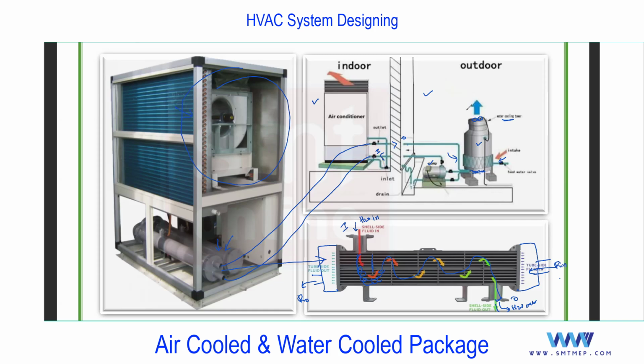How exactly, in detail, I'll show you at the time of the water cooled chiller. I'm just holding this because again the same thing will repeat. The cycle between the condenser and the cooling tower will remain the same as in the water cooled chiller. Whether you talk about a water cooled package or a water cooled chiller, the condensing side concept is the same. The condensing and cooling tower cycle is the same.